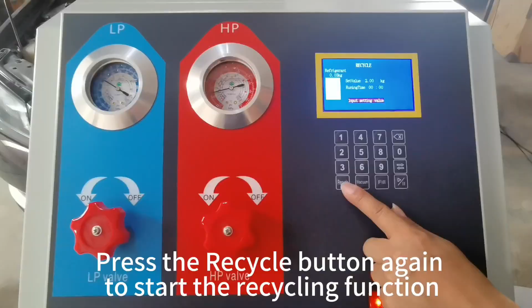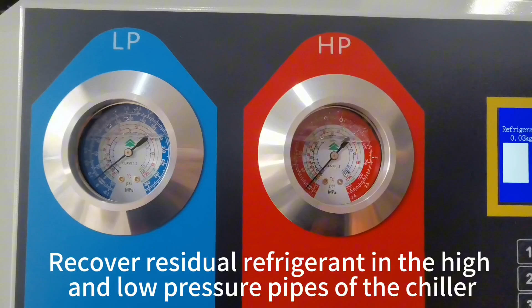Press the recycle button again to start the recycling function. Recover residual refrigerant in the high and low pressure pipes of the chiller. Finally, the site is cleaned up and the refrigerant recovery and filling process is completed. Next, I will introduce another way of filling. Refilling of small bottles of refrigerant and refrigerant storage tanks.